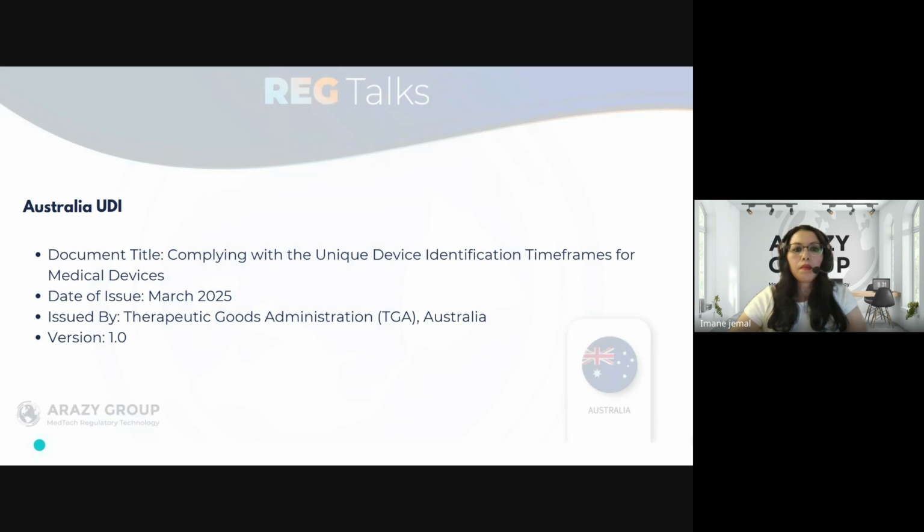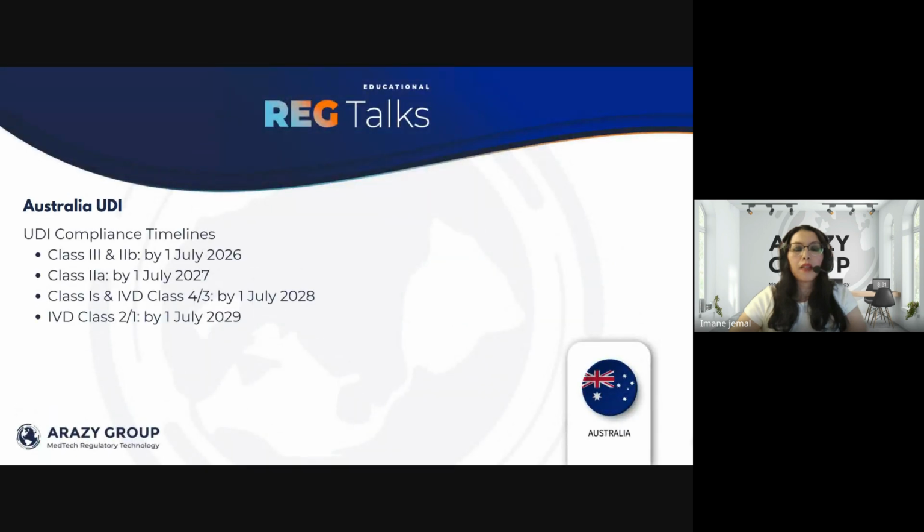We'll see the timeline for the applicability of UDI in Australia. There is a phased timeline to allow industry again to adapt. High-risk devices are prioritized, with low-risk devices given additional time, and submission of UDI data must occur within 30 days of supply.